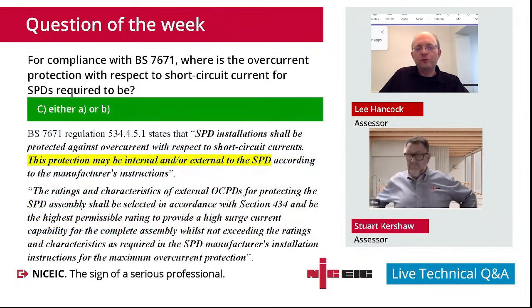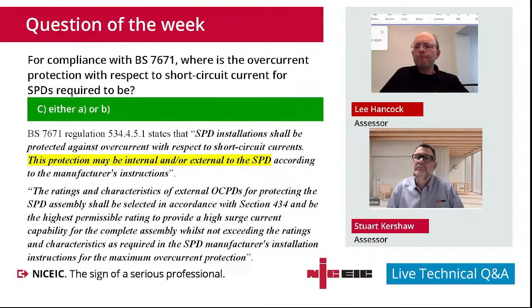Ultimately, when we're fitting these things, we've got to consider the manufacturer's guidance. We know where they want these things to be positioned within the DB, where they want, if there's external overcurrent protection, where that should be located. A lot of boards nowadays, you purchase them, they're already in. So contractors don't really have to concern themselves too much with this. But sometimes you may be retrofitting a consumer unit with one. And if the manufacturers want the device, for instance, next door to the main switch, sometimes they'll supply leads to connect into the bus bar arrangement, which are quite short, so they sort of dictate where the device has got to be. You've got to consider then where the overcurrent device has got to be. Sometimes that's next door to the main switch as well, which will mean you've got to shunt the other devices across somewhat to get the device in. But yeah, in essence, the answer is C. It can be internal and it can be external.